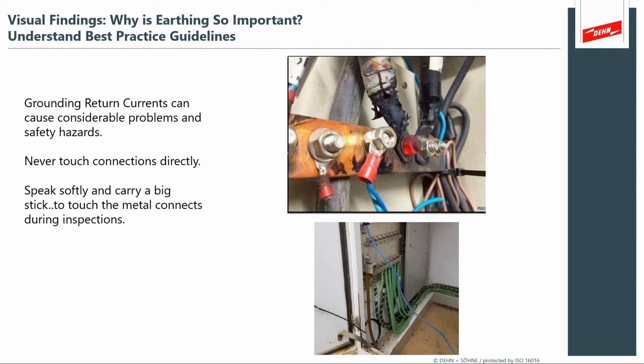I often do exactly that. I'll carry a small stick and I can bang on things and look for loose connections, because if you touch those loose connections and there's currents, you will feel it, and that's a safety hazard. So it's really important to understand how dangerous this can actually be. So here's a nice illustration of what looks like extremely well connected and best practices. Poor practices, best practice. It's good to understand the difference.